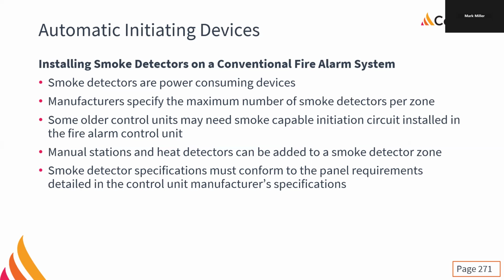But there's still a lot of panels from the 90s out there, so that could be an issue. If we have a lot of smoke detectors on a zone, we might be exceeding the power capacity of that initiating zone for it to function, especially if we have a lot of relay bases, because the relay base takes a little bit more power as well. So we might have to use four-wire smokes with the relay bases to make it all work properly.